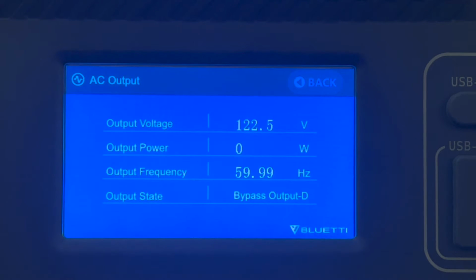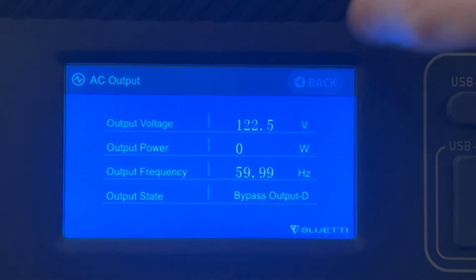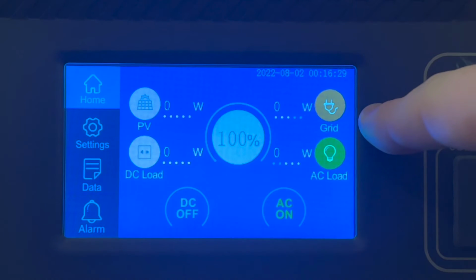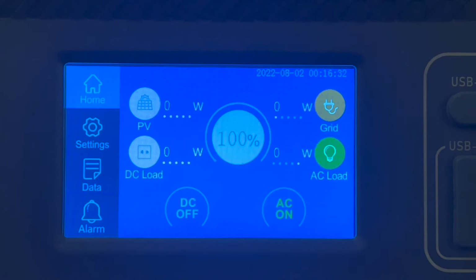Bypass output D means the grid is in bypass mode and is only supplying power to the load, basically meaning it's not charging the battery. Once I put some load on here, I'm going to run the battery down a little bit and you'll see it change modes.